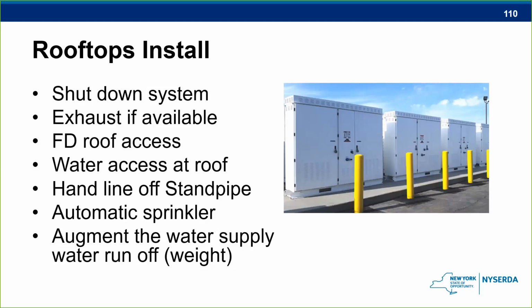Water access to the roof is a must. If the firefighters get up there, they want to have some sort of water access or their own protection line. So a standpipe going up to the top of the roof inside the bulkhead, where they can stretch a line off that, and the firefighters can feed that standpipe from outside. This way the firefighters can have their own protection line for themselves, making sure that if we have one of these cabinets on fire, it doesn't propagate to the cabinet that's adjacent to it.